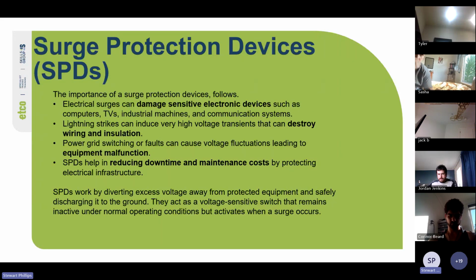So the importance of a surge protection device: electrical surges can damage sensitive electronic devices such as computers, TVs, industrial machines, and communication systems. Lightning strikes can induce very high voltage transients that can destroy wiring and insulation. Power grid switching or faults can cause voltage fluctuations leading to equipment malfunction. SPDs help in reducing downtime and maintenance costs by protecting electrical infrastructure. SPDs work by diverting excess voltage away from protected equipment and safely discharging it to the ground. They act as a voltage sensitive switch that remains inactive under normal operating conditions, but activates when a surge occurs.